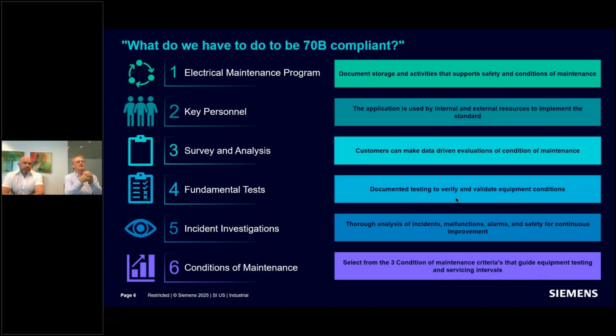The other thing is that key personnel who have to work with the electrical equipment or the 70B program, there are key people, both internal and external. With the facilities I helped work with, most of them, for example, didn't work with medium voltage that often. So we had a policy that if it was over 600 volts or 600 amps, since their experience was very limited, they weren't to do the maintenance on that, so we'd hire outside resources. Well, those outside resources also have to go by this 70B plan. That's one of the other key components.